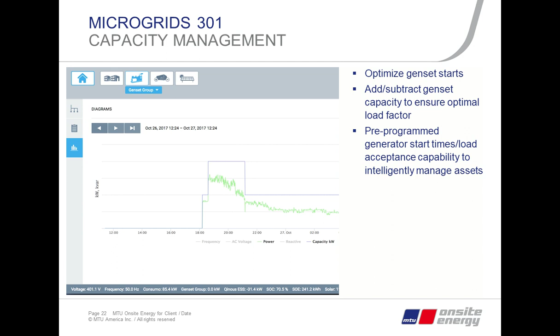Exactly — that's the intelligence where you shut off one unit to always ensure the optimum load factor. You could also pre-program generator start times to make sure a generator is online when you expect the need, so you don't have to wait for it to start up. There's a lot of intelligence you can apply to optimize when and how many gensets to use.